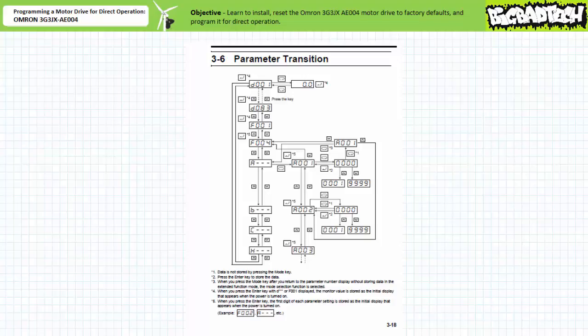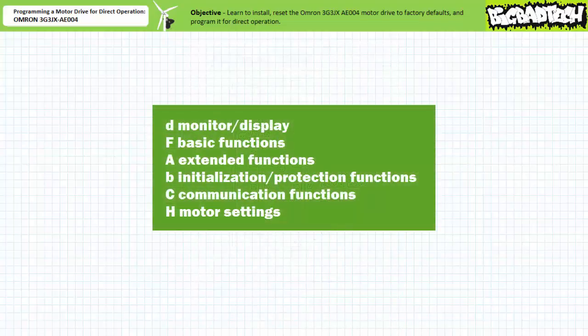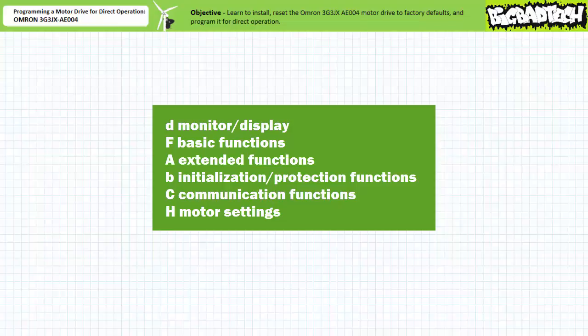This particular drive has a huge list of parameters listed in the manual, which I divide into several different classes: monitor or display functions preceded by a D, basic functions preceded by an F, extended functions preceded by an A, protection and initialization functions preceded by a B, communication functions preceded by a C, and motor settings preceded by an H.